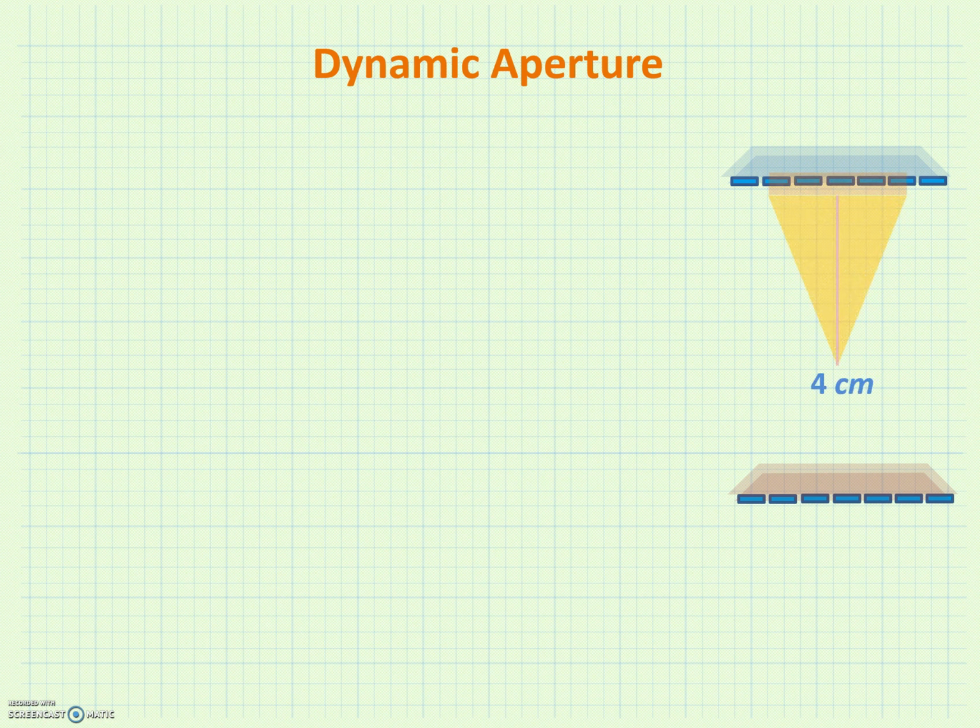So if you're insonating a deeper target, you can actually then widen the aperture, because as I mentioned, it's inversely proportional to the depth. So if it's deep, that means you're less susceptible to the spectral broadening error. So some manufacturers then have a wider aperture to sort of balance it out. And with the wider aperture, you get more imaging, or a broader imaging field. And so clinicians tend to like imaging, so often manufacturers will do this to optimize images.